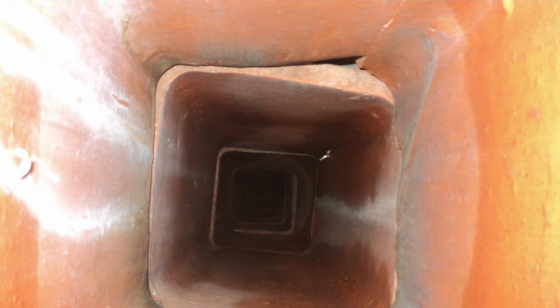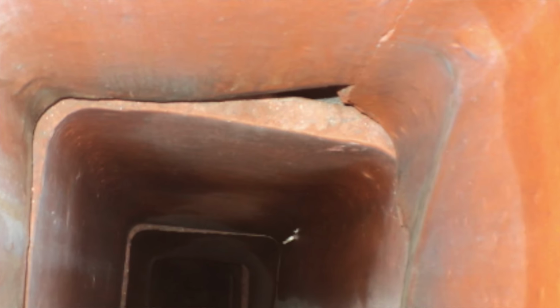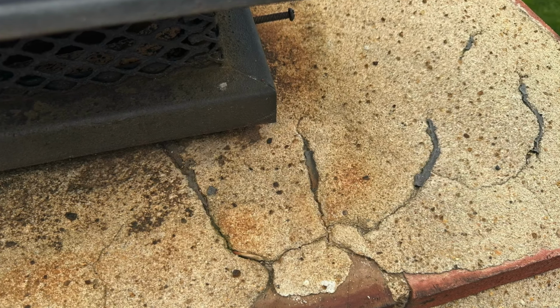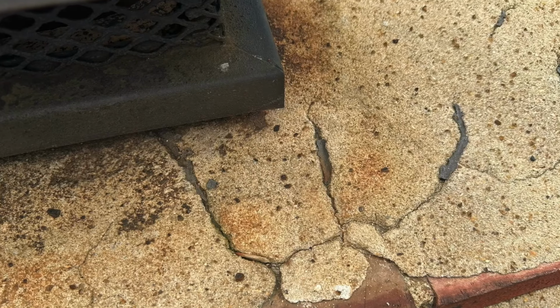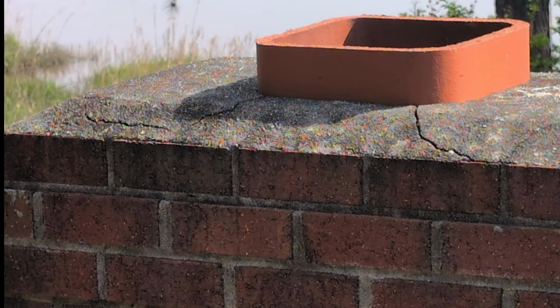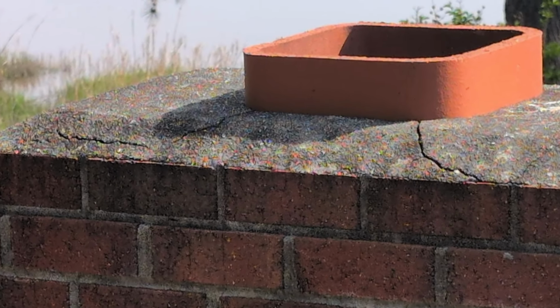The liner itself may also chip, spall, or deteriorate because vitrified clay has a very high modulus of elasticity, making it extremely stiff. When stiff materials are forced into movement but prevented from expanding, they transfer those stresses into the softer surrounding materials. This is why the crown, mortar joints, and masonry, being comparatively weaker, tend to fail first.